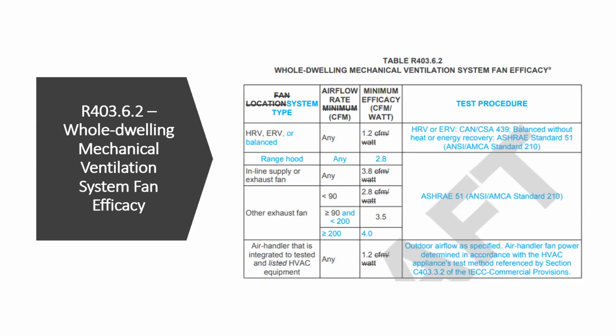So test procedures, they've also put those in. In prior code cycles, there wasn't a test procedure listed, so a lot of people had to ask, there's no consistency there. How do I determine its CFM per watt being used? And so now there's a way to follow a standard process that's listed here on how to do it. Of course, the ERVs and HRVs are the ASHRAE standard 51. There's also a standard 210. And then you've got range hood, inline supply fans, either exhaust or supply, and other exhaust fans, which need to also follow the ASHRAE 51. And then you've got air handlers. It says outdoor airflow as specified. Air handler fan power is determined in accordance to the HVAC appliance testing method referred to in this commercial section on how to test the HVAC for that power wattage.